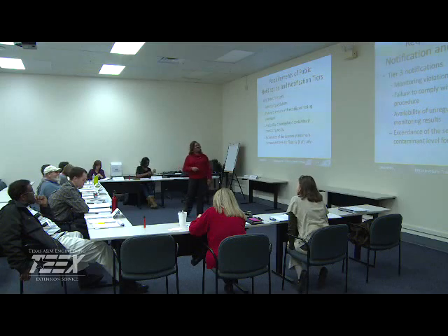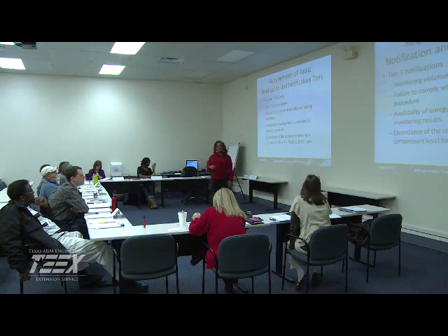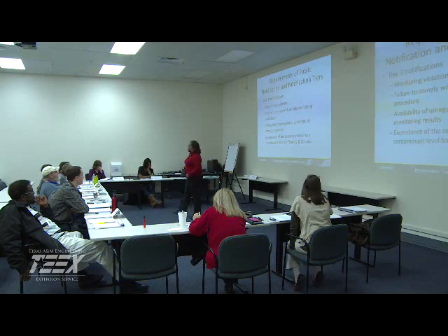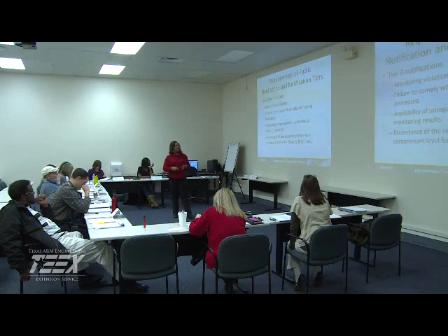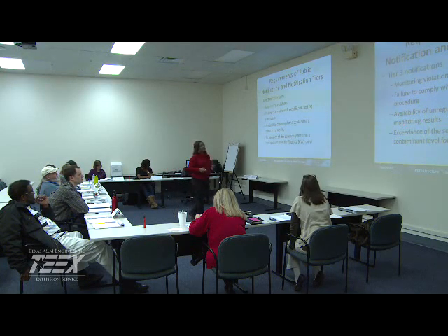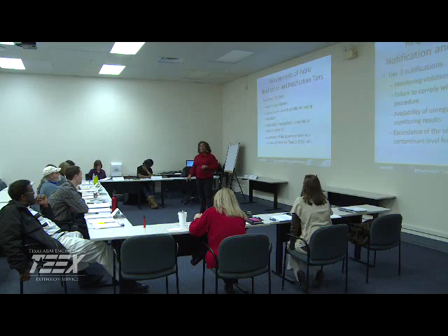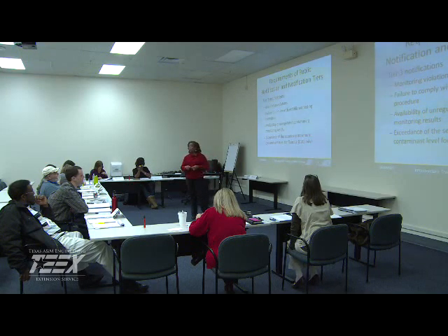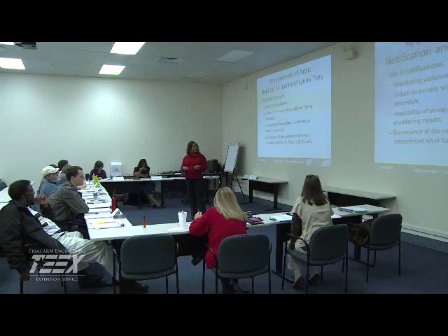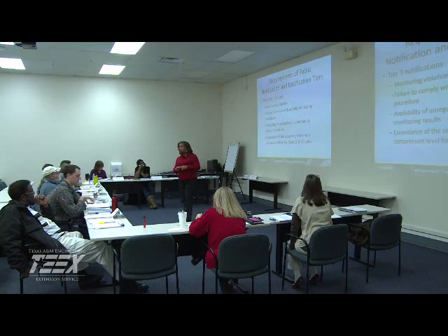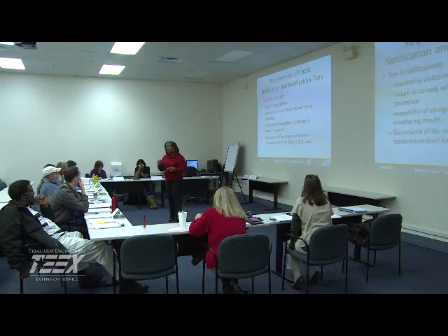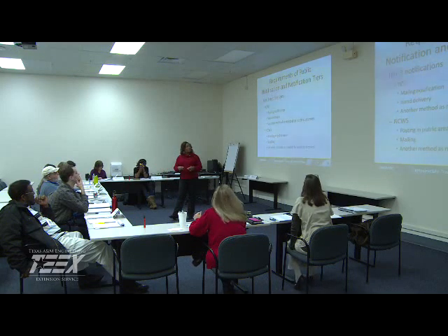Tier 3 notification: any monitoring violations, failure to comply with established testing procedures. Anything we report must use an approved method. Availability of unregulated contaminant monitoring results — if that is a requirement, you're supposed to be monitoring something that's not on the regulated list, you've got to do it and keep the results. Exceedance of a secondary maximum contaminant level for community systems — that's for fluoride only. In this case, the secondary does matter. Same methods of delivery as with Tier 2s.